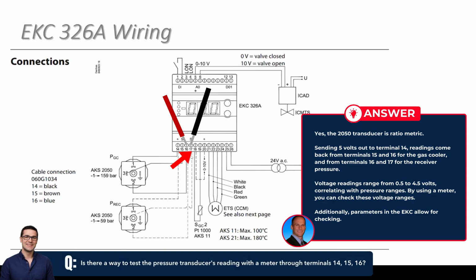It looks like you should be able to read a voltage back from that transducer in either case, and it's going to be between a range of 0.5 volt and 4.5 volts. Kind of similar to what we talked about on the 0 to 10 signal to the high pressure valve, that voltage is going to fall somewhere between 0.5 volt and 4.5, and you can correlate that to your pressure range, either the -1 to 159 or -1 to 59 bar. So if you're using a meter, then you can see what that voltage range is there. And then we'll show in a few minutes where there are some parameters in the EKC as well, where you can also check what pressure reading the EKC thinks you're getting.